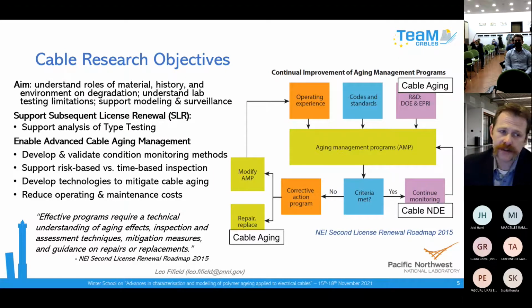So our objectives are also to support and develop methods for condition monitoring, like dielectric spectroscopy, frequency domain reflectometry, and others, to support risk-based inspection rather than time-based inspection. If you test cables that you have reason to believe will be degrading, it's more efficient than just testing them based on the calendar. And additional goals are to develop technologies to mitigate cable aging, like cable rejuvenation, treatment of cables to extend their life. And with the cost pressures, the goals of these NDE techniques are also to reduce the operating costs in maintaining plants.